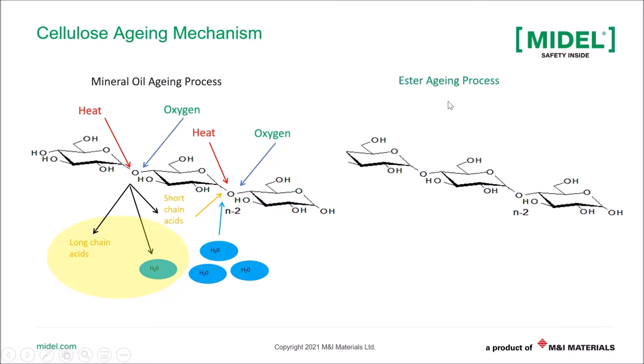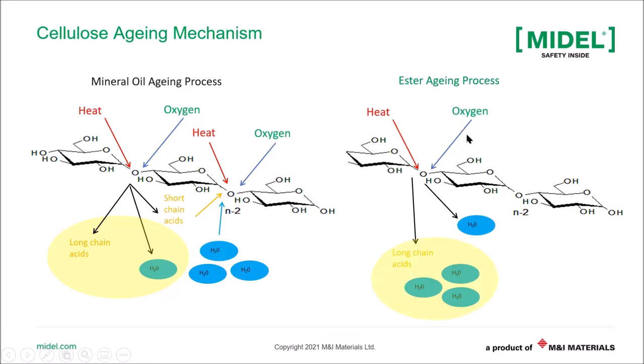So in the ester aging process, you have the same cellulose material, and you still have the heat and oxygen. But in an ester liquid, due to the difference in the chemical structure, there are long chain acids produced and more water is actually held in the insulating liquid, and less of the water becomes available to add to the continuous breakdown of the cellulose chain. Because of this, the aging rate of cellulose in ester liquids is slower.